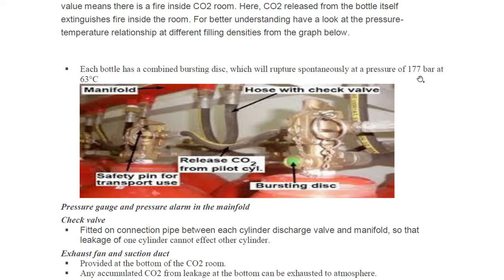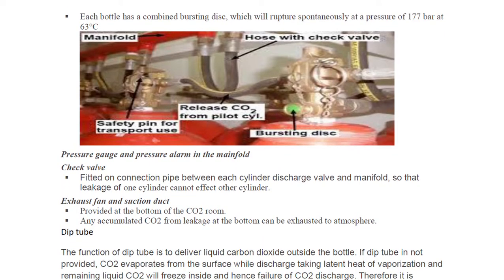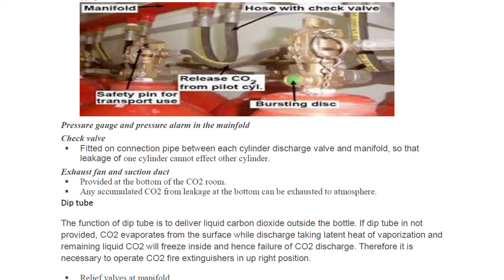Each bottle has a combined bursting disk which will rupture spontaneously at a pressure of 177 bar at 63 degrees Celsius. You should also know that the CO2 room has a heating arrangement when in colder climates, with insulations provided.